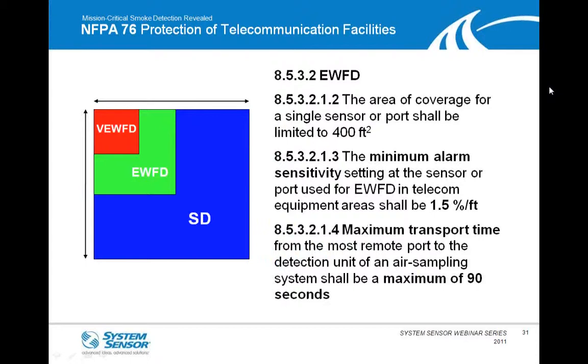Continuing on with early warning, just the way the standard is laid out, it starts with very early warning and then backs off to early warning. Much like with very early warning, where sampling point coverage could be at 200 square feet, early warning is a little softer, and coverage can be limited to 400 square feet. The minimum alarm level, instead of being 1% per foot as with very early warning, can go up to 1.5% per foot. And the maximum transport time for early warning is extended up to 90 seconds. So to recap, for very early warning, 60 seconds transport time. For early warning, we're at 90 seconds. And for standard detection, 120 seconds. Again, this is if you're using aspiration to meet the NFPA 76 requirement.